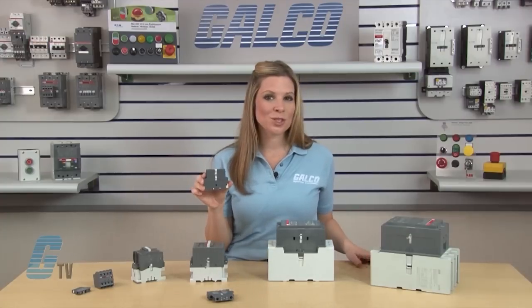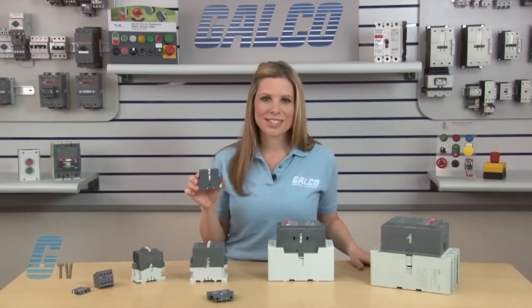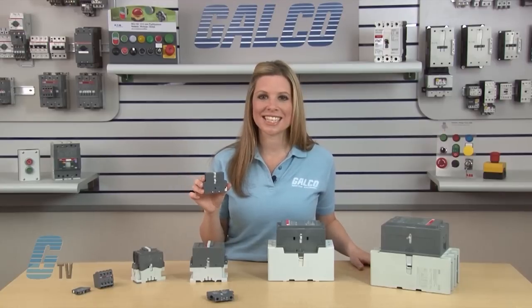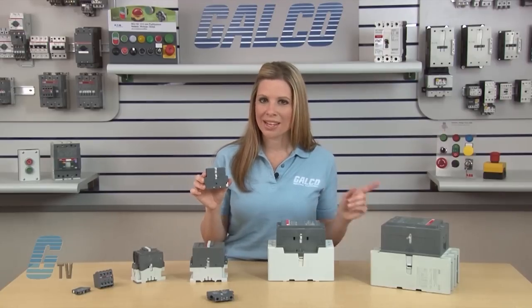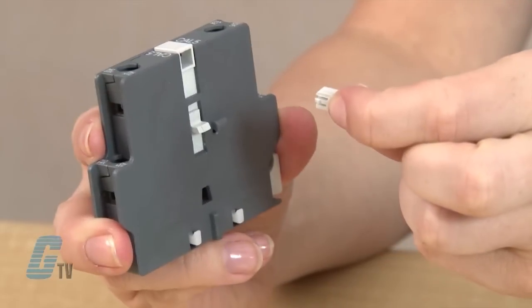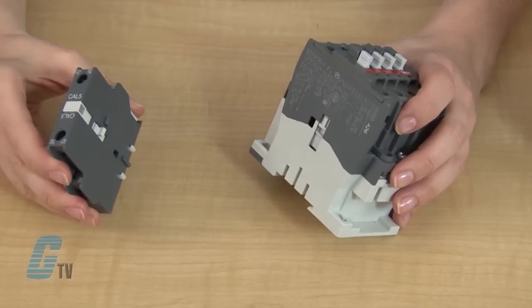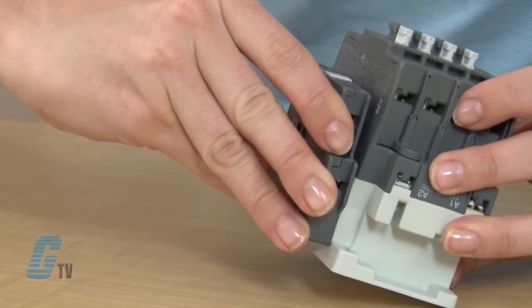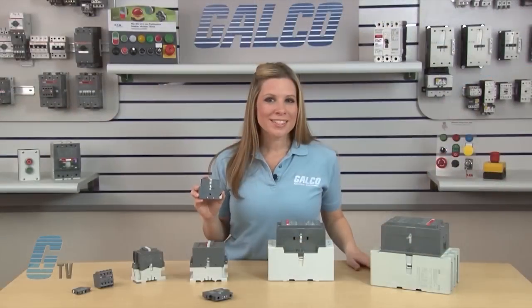The CA5-11 can be installed three different ways depending on the model number. Models A or AE-9 through 26 and models UA-16 through 25 do not need the plastic peg in the upper middle part — this piece can be removed without the use of any tools. Install the Auxiliary Contact by aligning the plastic hooks with the grooves on the side of the contactor, then lift up the Auxiliary Contact until it snaps into place.